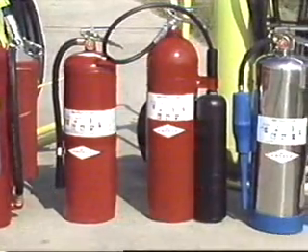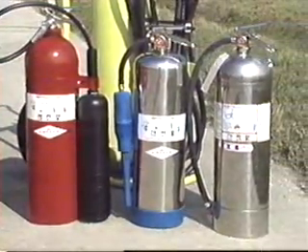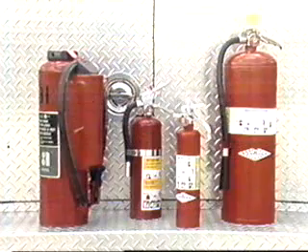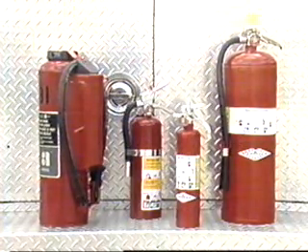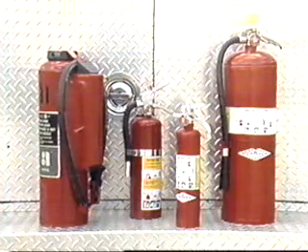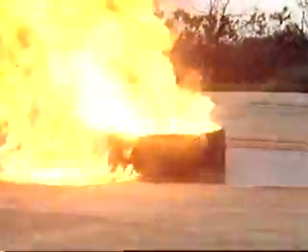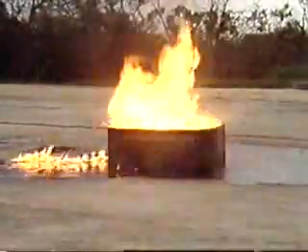Extinguishers suitable for different fires are categorized in the same manner as the class of fire they work on. To help identify a proper extinguisher, two types of systems have been developed. One uses a letter and shape for each of the four classes of fire. The other uses pictures identifying both the fires the extinguisher can be used on and the fires it cannot. While certain extinguishers like multipurpose dry chemical can be used on A, B, and C fires, no extinguisher is effective on all four classes. In fact, extinguishers designed for one class may be extremely dangerous when used on another. For example, a water extinguisher is not recommended for use on a Class B flammable liquid fire, because it may spread the fire.